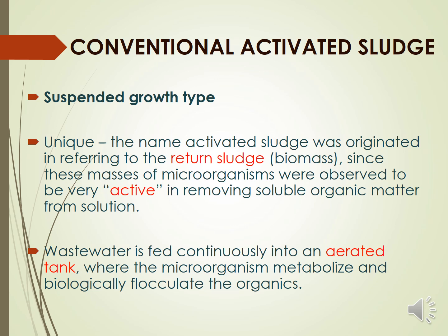The conventional activated sludge system is considered a suspended growth system. In chapter six we discussed two types of biological processes: suspended growth and attached growth. In suspended growth, the microorganisms float and mix together with the wastewater in one tank. In attached growth, the microorganisms are attached or stuck to certain media, such as plastic or wood. The conventional activated sludge system is suspended growth because the microorganisms mix together in the aeration tank.